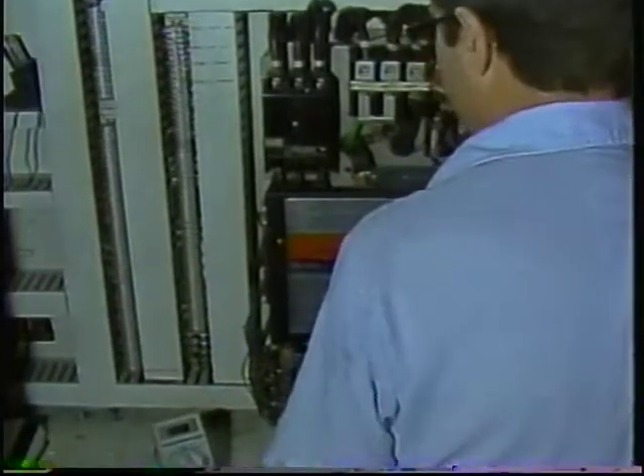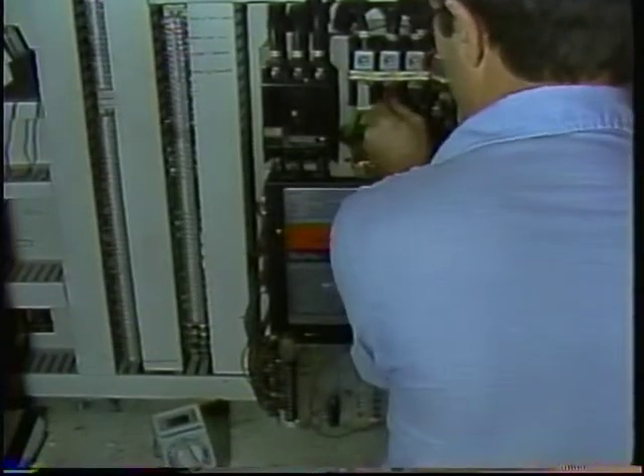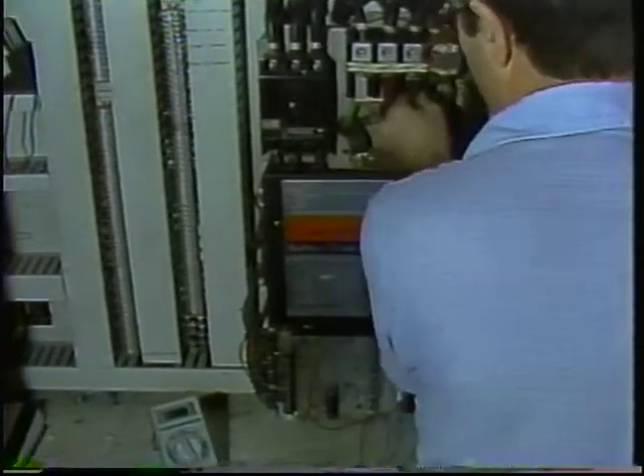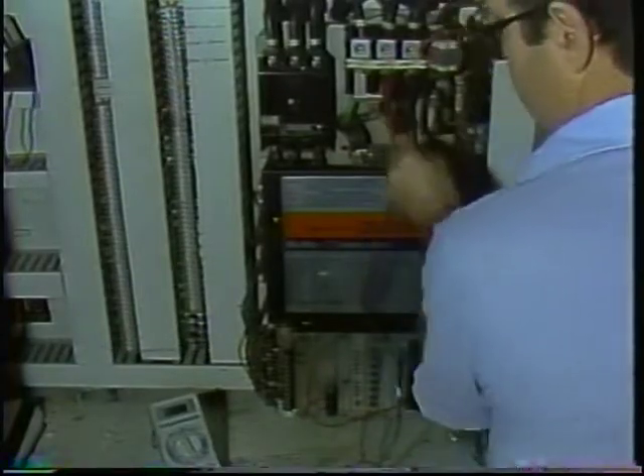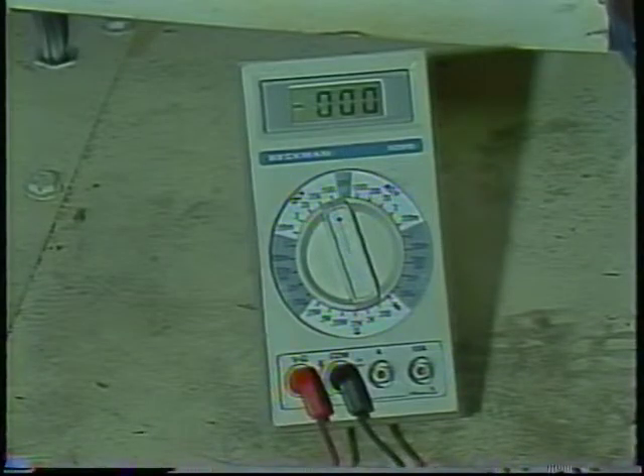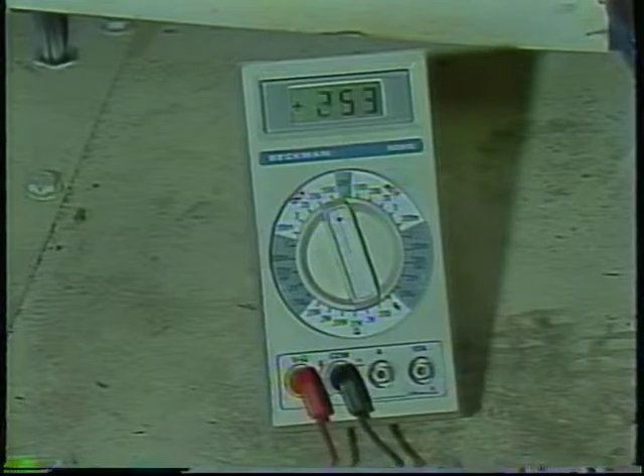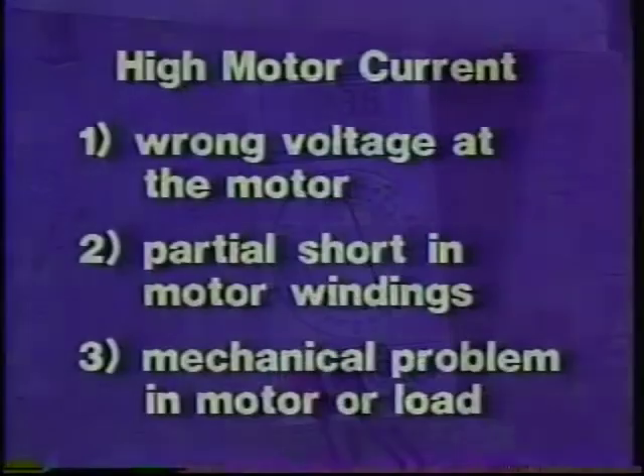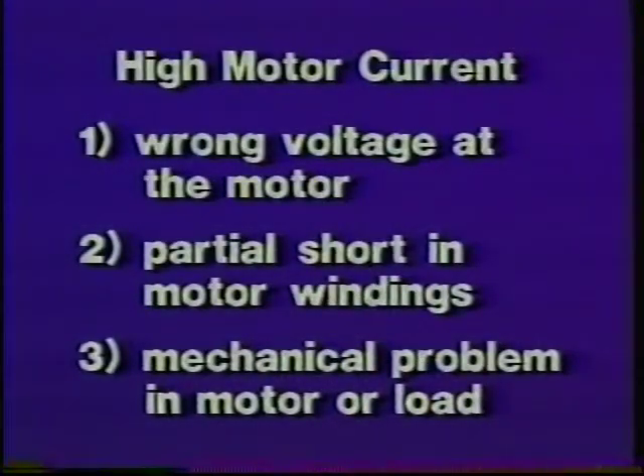Many motors are controlled by starters which are supposed to provide a voltage which increases gradually or in steps as the motor accelerates. Determine if the starter is providing the motor with full voltage when it should. If it is not, the motor may draw too much current and trip its overloads. If the voltages to the motor are okay, you have eliminated supply voltage as a probable cause. Now you need to try to eliminate either the motor or the load with tests. The tests depend on the motor type.